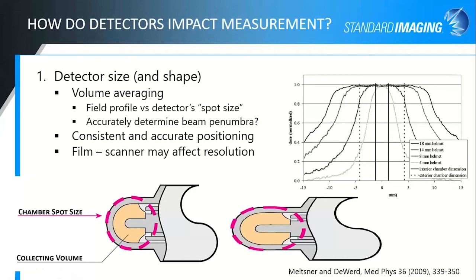So then the detectors themselves can impact your measurements as well. One of the first ways that I usually talk about is detector size and shape, the first factor to consider when you're looking at the impact of the detectors on your measurement. There's always some volume averaging that's happening with a detector. There is no such thing as a perfect point detector. So you need to understand your detectors. For something like ion chambers, you need to understand if your spot size for your chamber is spherical, so the orientation within this profile doesn't matter so much. Or if you've got an elongated profile for the spot size of your detector, the area over which it's measuring, in which case the integration over the field transverse to your detector compared to in line with your detector is different. And so your volume averaging, depending on the size of your fields and where you're making those measurements, will affect your measurements as well.